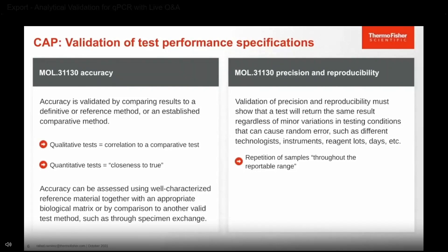In terms of precision and reproducibility, it must show that the test will return the same result regardless of minor variations in testing conditions that cause random error, such as different technologists, instruments, reagents, and even days. It's important to have enough repetition of samples throughout the reportable range to establish this.